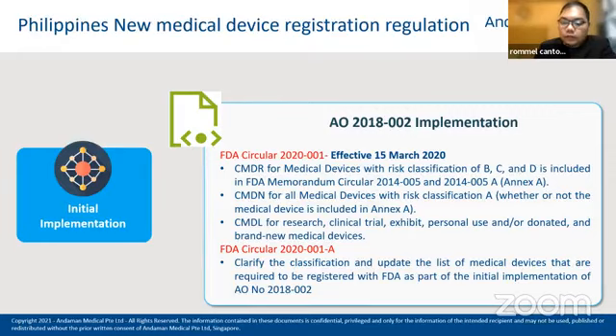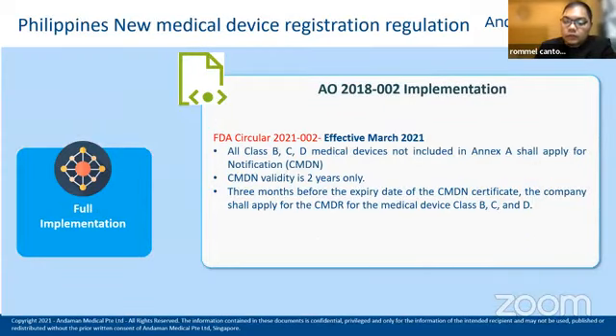Next, this circular was amended by FDA Circular 2020-001-A, which clarified the classification and updated the list of medical devices that are required to be registered with FDA as part of the initial implementation of AO number 2018-002. It comes to a point that we undergo the full implementation, and it took effect in March 2021, a year after the initial implementation. It was issued under FDA Circular 2021-002.